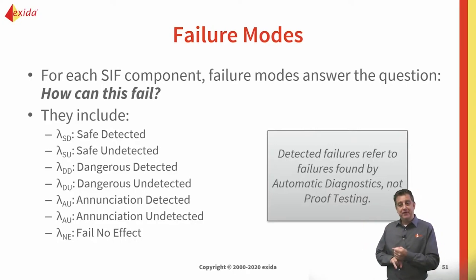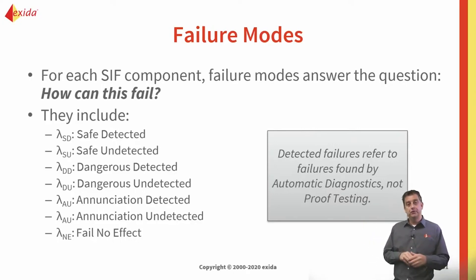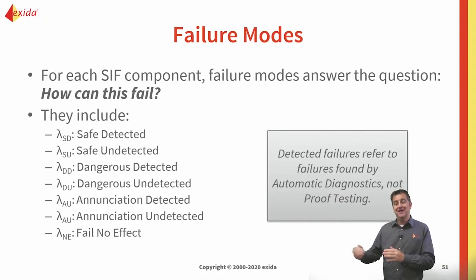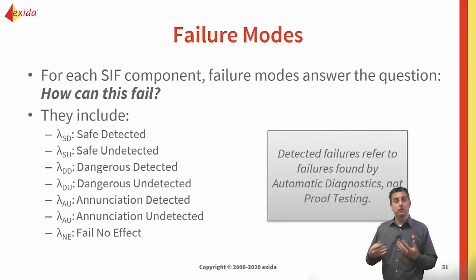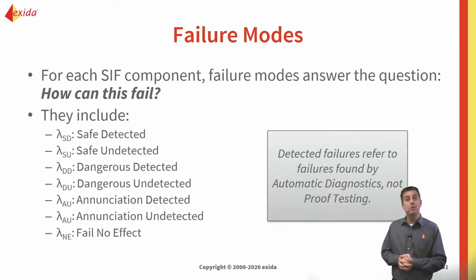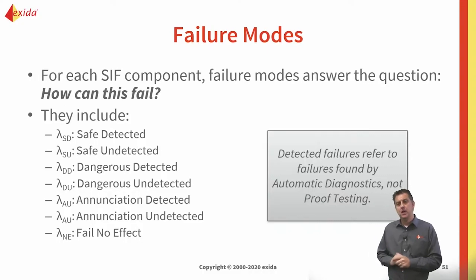There are also annunciation failures, both detected and undetected, which refer to failures of diagnostic circuitry. If the diagnostics fail in such a way that they're no longer able to identify future faults, that's an annunciation undetected failure. They could also give a false positive — indicating something is wrong even though nothing is — which is an annunciation detected failure, potentially prompting an unnecessary repair action. That gives us a total of seven failure rate categories typically considered in SIL verification.